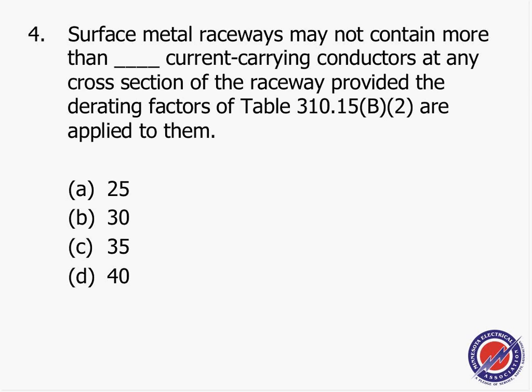Surface metal raceways may not contain more than how many conductors? Number 4 is B. Now remember, we're talking about surface metal raceways, 30 conductors. Otherwise, you have to apply 310.15(B)(2). So 30 conductors at any cross-sectional area, provided the derating factors are applied to them. I emphasize, guys, for metallic and non-metallic raceways, I can put as many conductors as I want, as long as, if I want not to derate, I limit the current-carrying conductors, the hot conductors and the neutral that carry current, to 30.